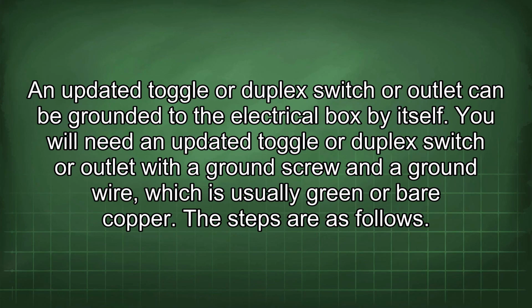An updated toggle or duplex switch or outlet can be grounded to the electrical box by itself. You will need an updated toggle or duplex switch or outlet with a ground screw and a ground wire, which is usually green or bare copper. The steps are as follows.